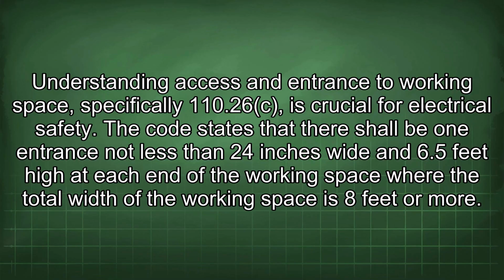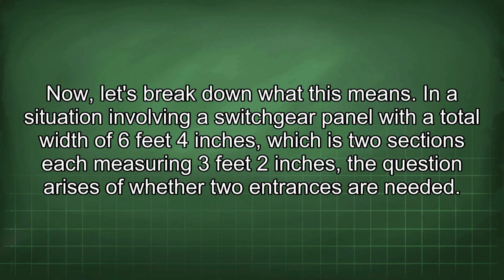Understanding access and entrance to working space, specifically 110.26, is crucial for electrical safety. The code states that there shall be one entrance not less than 24 inches wide and 6.5 feet high at each end of the working space, where the total width of the working space is 8 feet or more. Now, let's break down what this means.